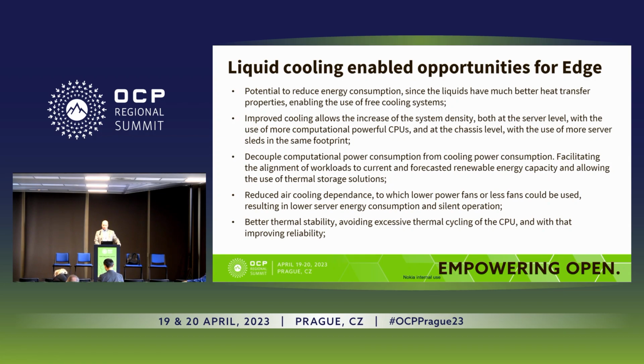We can move heat in a much more efficient way, and with higher temperature of liquid, and with that way we can enable free cooling in many environments where it's not possible with air heat transfer. We can increase system density. We can put more servers to the same rack, or we can put more power to the single server. And with that way, we can increase computing capacity of system.